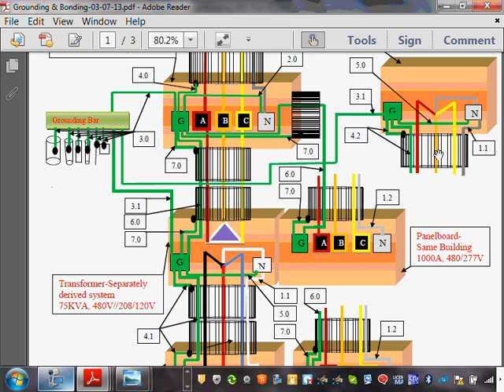If your generator, like major equipment, when we parallel them, does not have a circuit breaker here, you pull these conductors all the way to the switch here, and the first circuit breaker you put is right in the switch here. When we parallel generators with big stuff, then this conductor becomes a supply side bonding jumper. And what's the difference? The size is different.